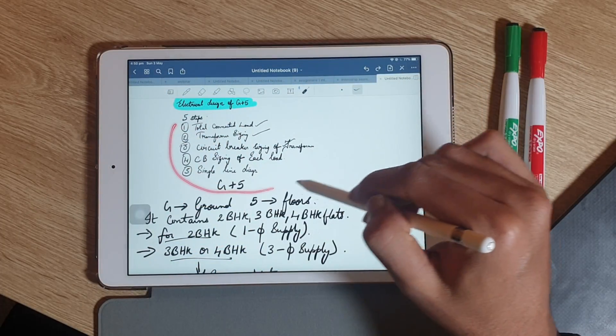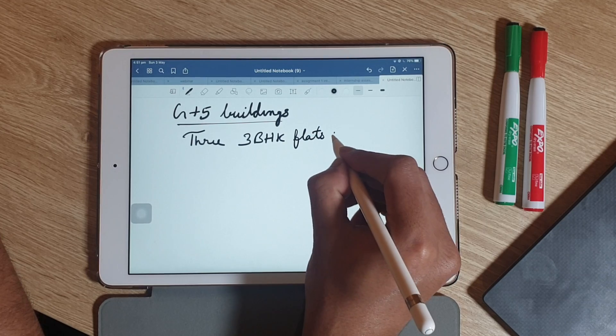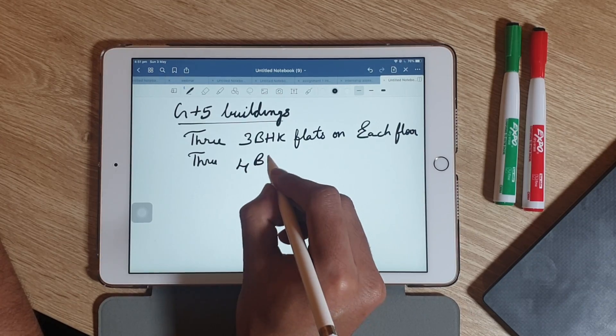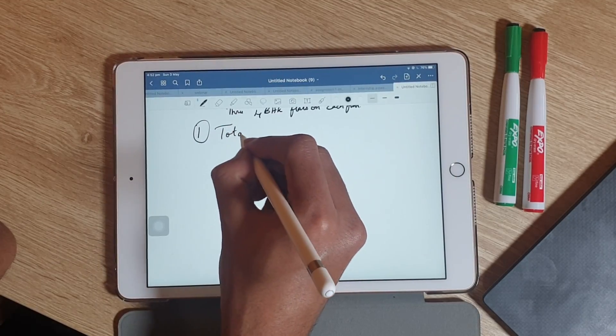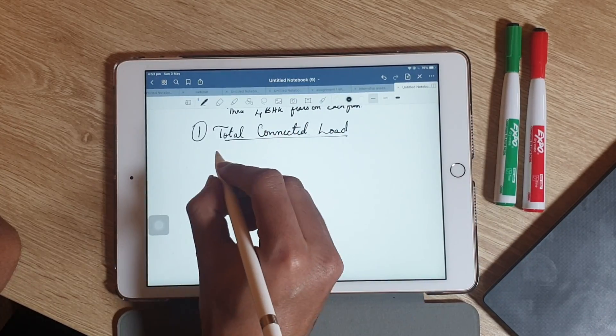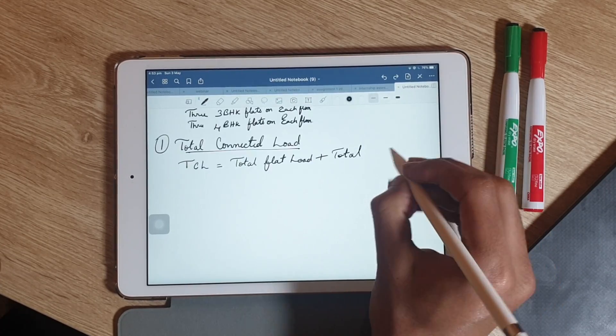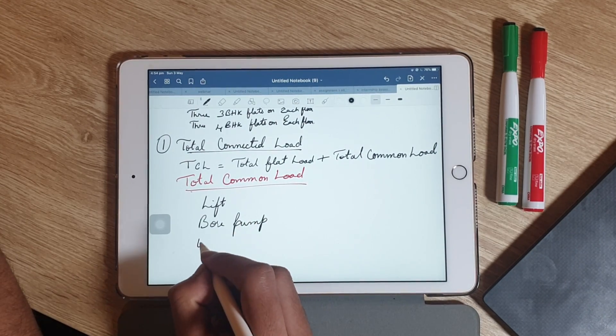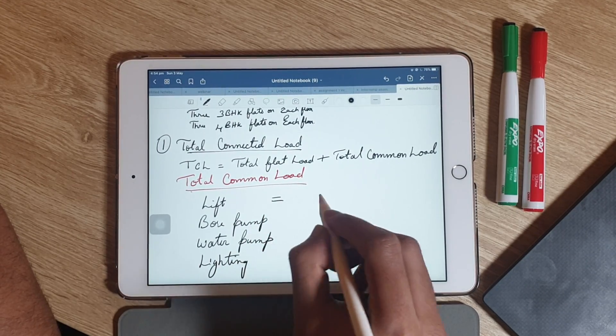Let's start with the 5 steps for designing the G plus 5 building. We assume this building has 3 BHK flats on each floor, giving a total of 15 three-BHK flats, and 3 four-BHK flats on each floor, giving a total of 15 four-BHK flats. The first step is calculation of total connected load, which equals total flat loads plus total common load. Total common load includes lifts, bore pumps, water pumps, and lighting for the lobby area and garden.